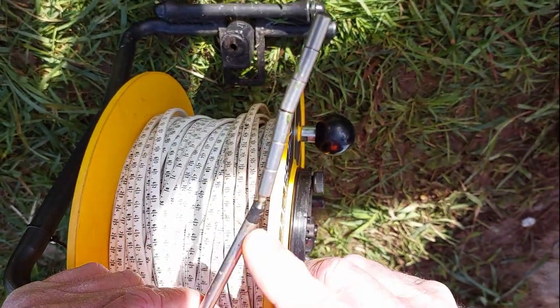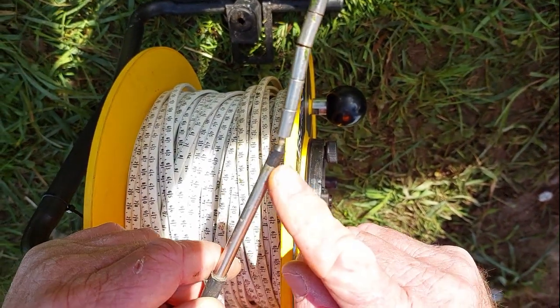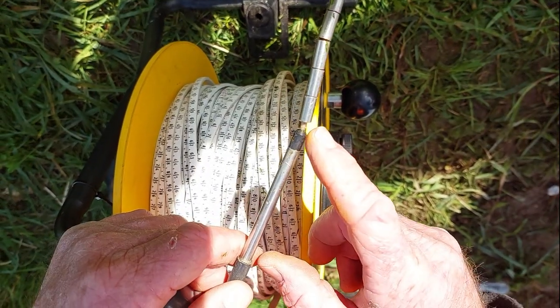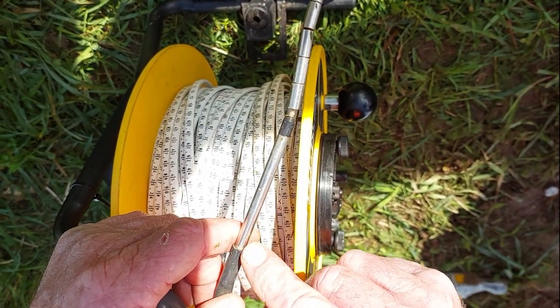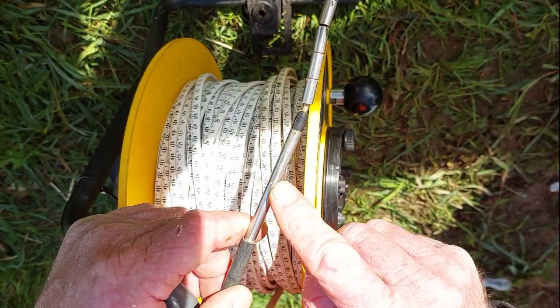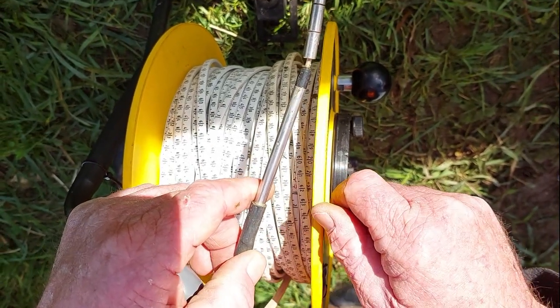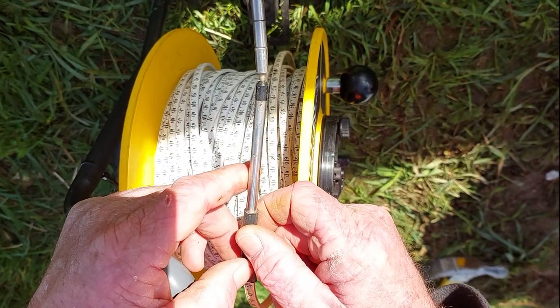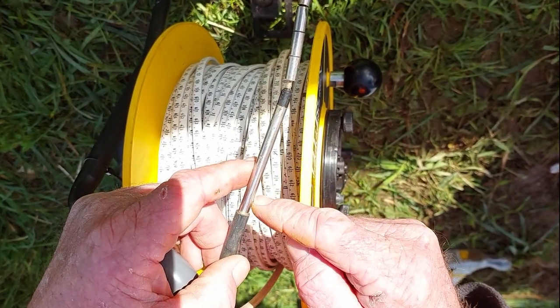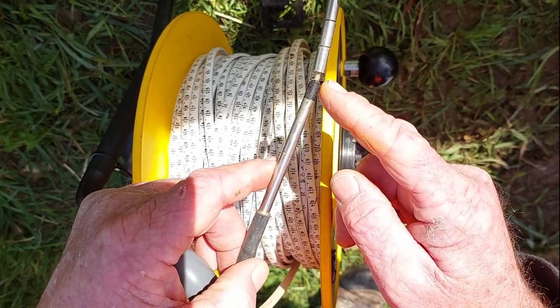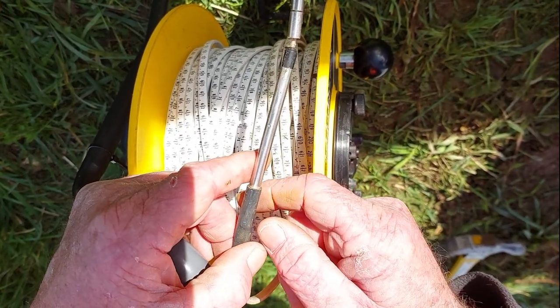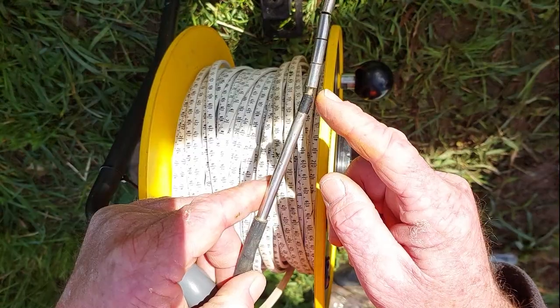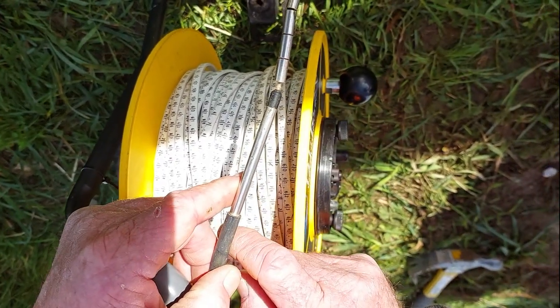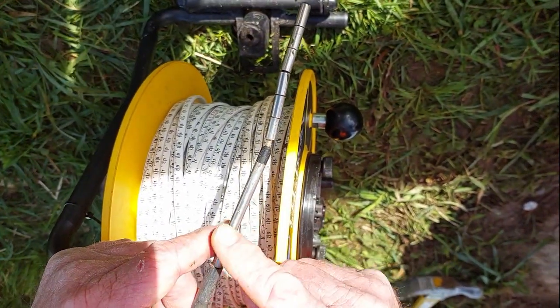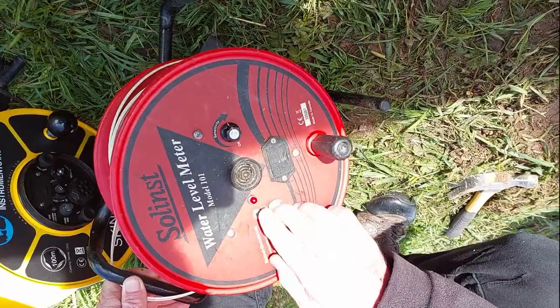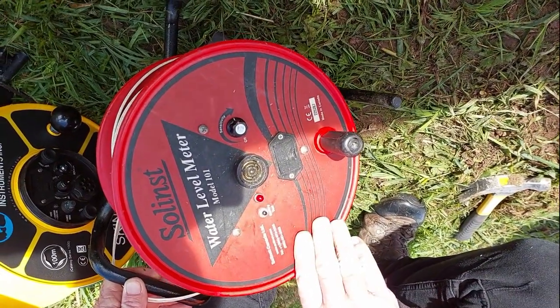We do have issues with these sensors at times. They're highly reactive, particularly in a narrow piezo. If they touch condensation on the side of the piezo pipe, they'll start to react and make a bit of noise as if they were actually measuring water level. You do have to be careful that you are actually measuring water level, and sometimes it can take a bit of jiggling around before you're really confident that you are actually touching water level and not some form of interference on the probe itself. So that's how you check your battery.